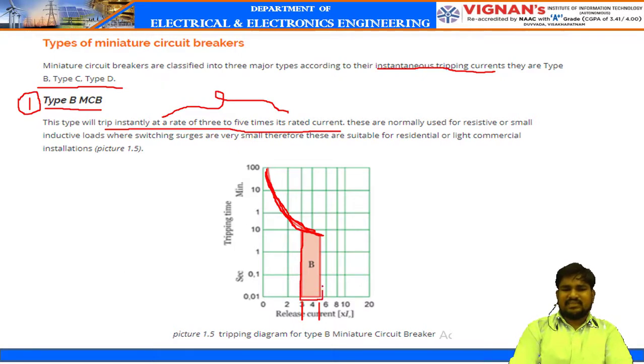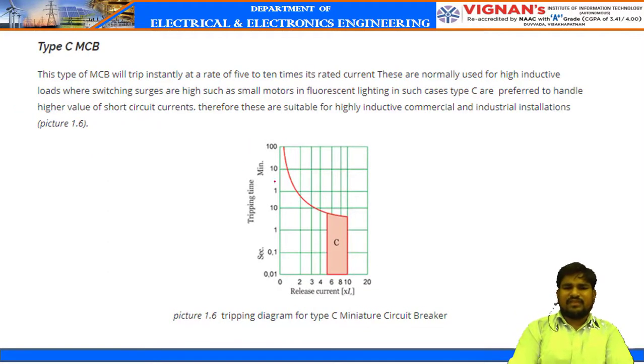This is the short circuit fault. So in this fault, within no time, whenever the fault occurs, the current increases all of a sudden. So if this current is in between 3 to 5 times, we use type B MCB.